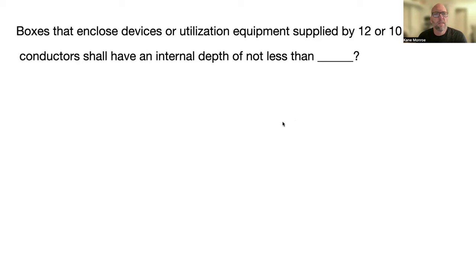Boxes that enclose devices or utilization equipment supplied by 12 or 10 AWG conductors shall have an internal depth not less than one and three sixteenths inches, 314-24-B-4.